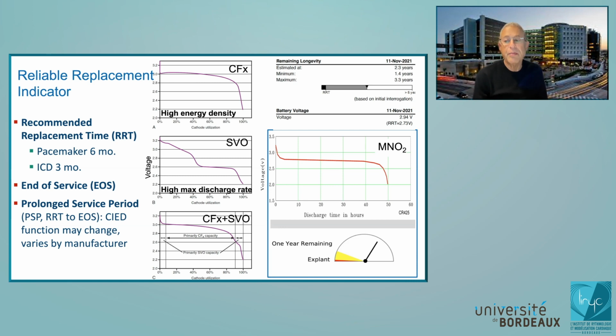Different battery chemistries have different replacement indicators, and we should know that for the technology we're using. So for example, if you look at a Boston Scientific battery, the battery voltage is not a reliable indicator of when the battery is going to fail. That's why they actually count the charge the battery has delivered over its lifetime and have a little meter that shows that to you.